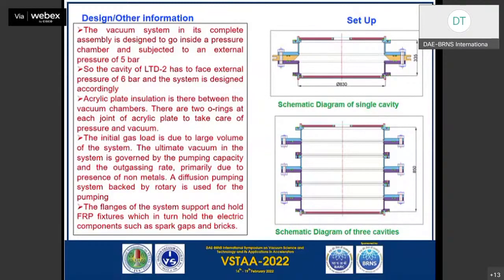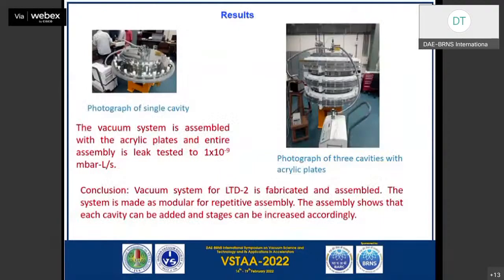In the last slide, you can see the system completely assembled: one single cavity being leak tested here, and three cavities being leak tested here. We have leak tested the system to 1 into 10 power minus 9 millibar liter per second, at individual stages and at the final stage. Now the pressure chamber has also arrived. Since it is different from others, we have used two o-rings radially, one inside and one outside.